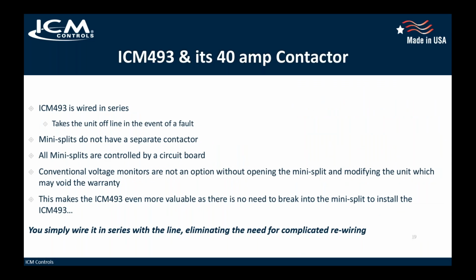All right, so some key points again. The ICM 493 is wired in series, so it takes the unit offline in the event of a fault. Because mini splits don't have a separate contactor, you really can't break into those with something like a 492. You could be voiding a warranty with these conventional voltage monitors. That's why the 493 is nice with mini splits, because you don't have to break into the equipment. You can just put it in series with the main line. So the power comes from the distribution box to the ICM, from the ICM right to your mini split, and you're good.